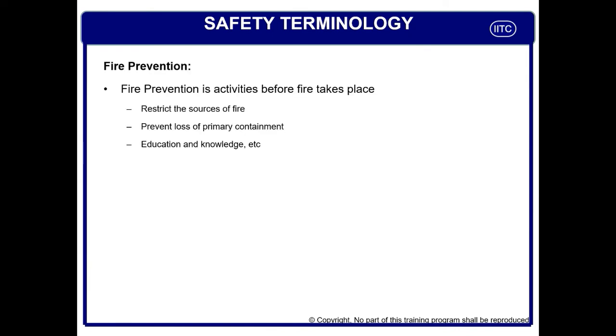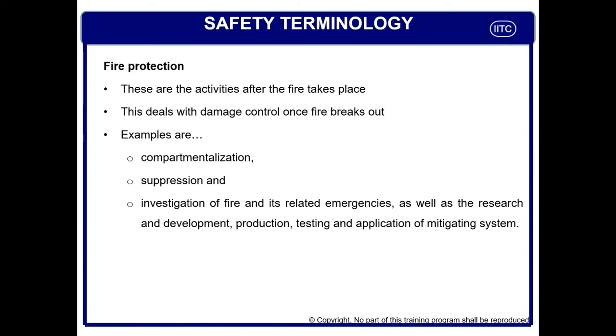There are two terminologies used in fire. One is fire prevention and the second is fire protection. Fire prevention covers activities which come before fire takes place — like restricting fire sources, preventing loss of primary containment, and education. Fire protection means activities that come after fire takes place. Once fire happens, what actions ensure there is no major damage — for example, compartmentation of combustible material, suppression systems to remove oxygen, fire investigation, identifying root causes, and implementing fire control recommendations. These are fire protection measures.